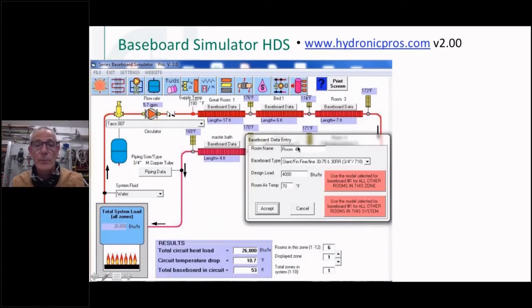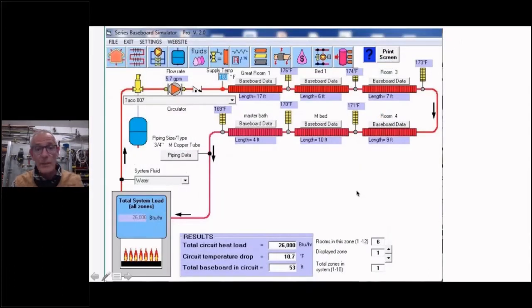So there's an example where I can put a room name in there. I can put the type of fin tube I wanted to put in there, put my design load and put that in. And then once I accept that, this is what you end up with. So it shows me all the different lengths in all those different rooms as I go through the loop here. And I can play around with that. I could pick a different circulator pump. I could go a bigger pump. I could go a smaller pump. I could change my supply water temperature.